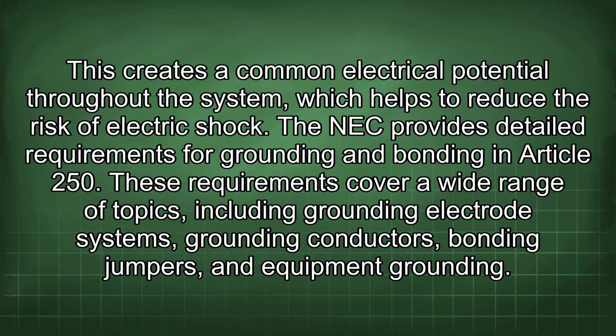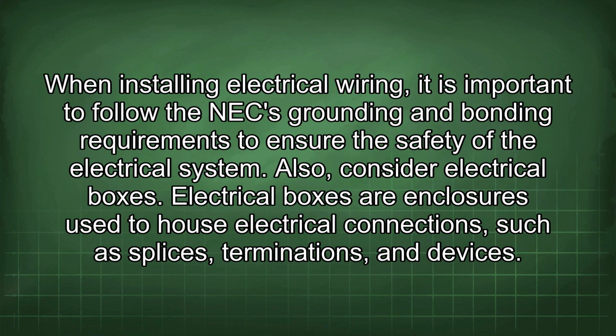This creates a common electrical potential throughout the system, which helps to reduce the risk of electric shock. The NEC provides detailed requirements for grounding and bonding in Article 250. These requirements cover a wide range of topics, including grounding electrode systems, grounding conductors, bonding jumpers, and equipment grounding. When installing electrical wiring, it is important to follow the NEC grounding and bonding requirements to ensure the safety of the electrical system. Also, consider electrical boxes.